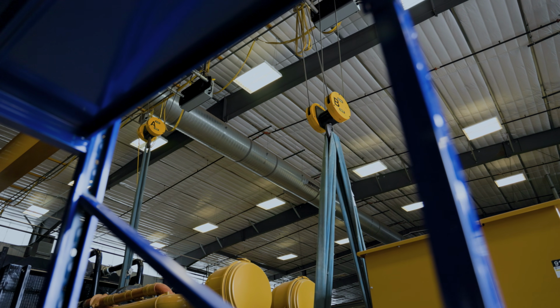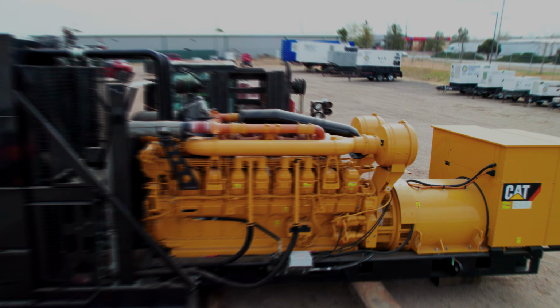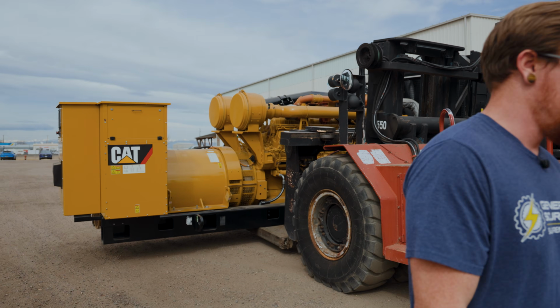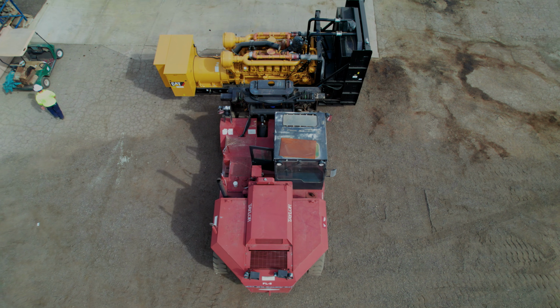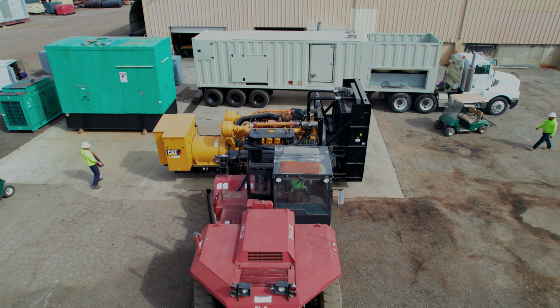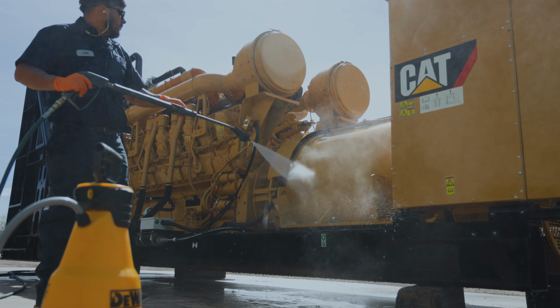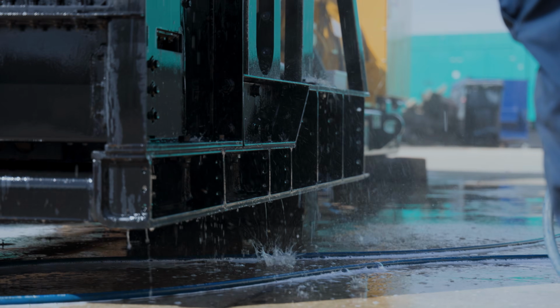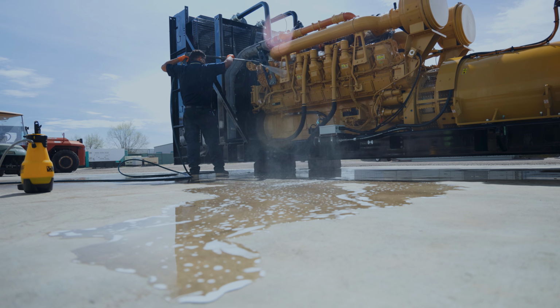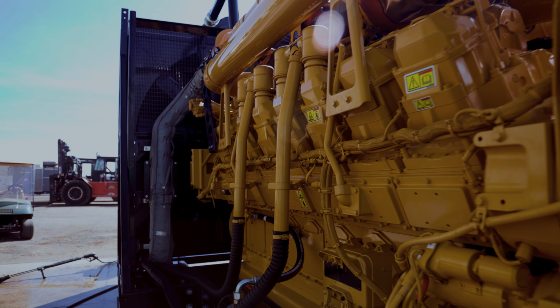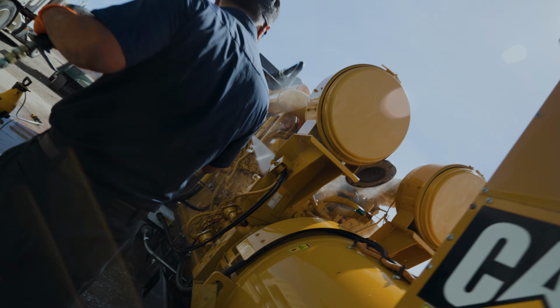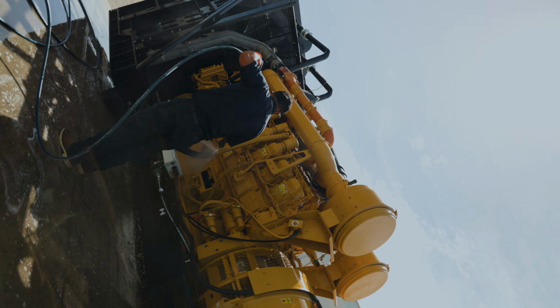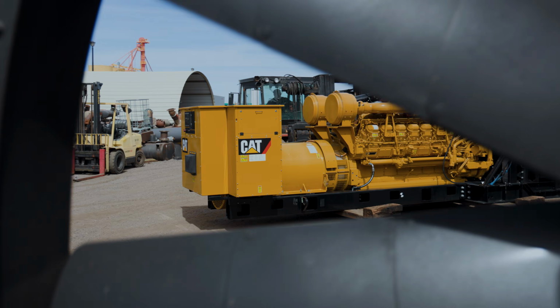A megawatt class generator can run into the millions of dollars. So today we're going to talk about the one best practice to protect your investment. Throughout the year, the generator is typically on an exercise program that is set up to kick on for 20 minutes once a month, maybe even once a week. With that being said, it's not put under load or very little load. We're risking the carbon and diesel fuel buildup in the exhaust manifold.